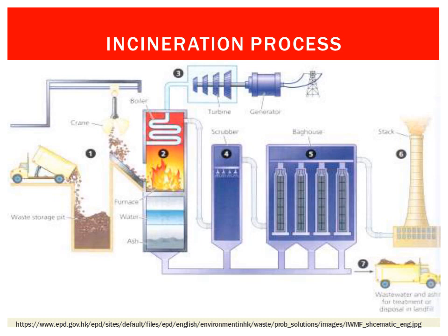Other gaseous pollutants may include furans, dioxins, hydrogen chloride, and hydrogen fluoride, depending upon the composition of the waste. These gaseous pollutants are removed by various systems like cyclones, wet cleaning systems such as scrubbers, electrostatic filters, and bag filters — when used collectively these are termed a bag house. Ultimately, these scrubbers and bag houses remove the suspended particles and release clean air into the environment. This is the overall incineration process for burning waste and utilizing the energy generated.